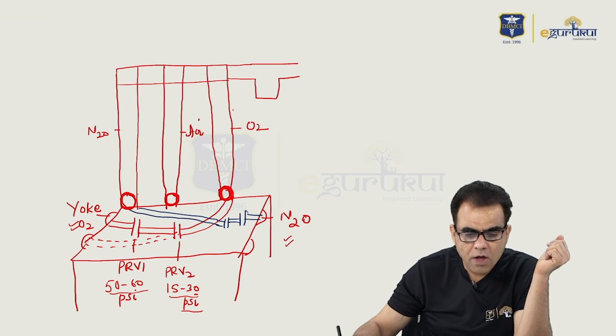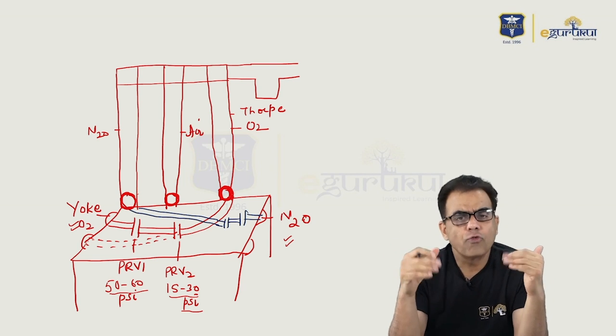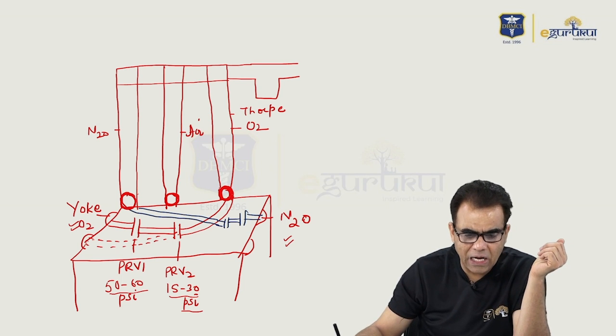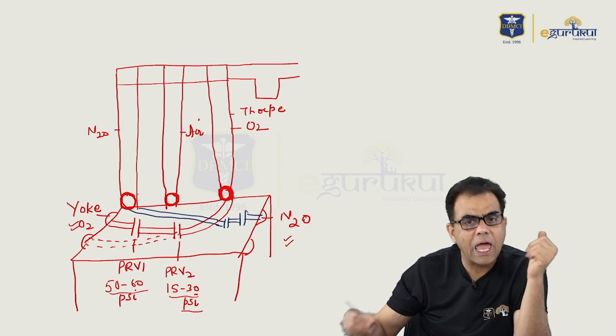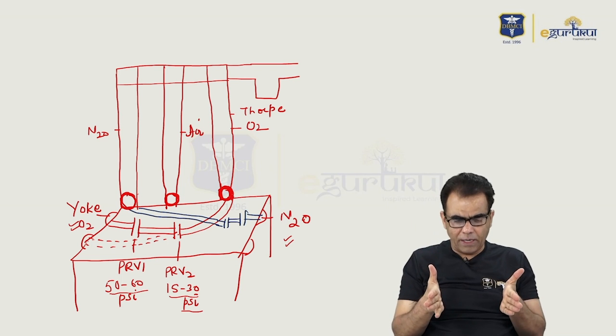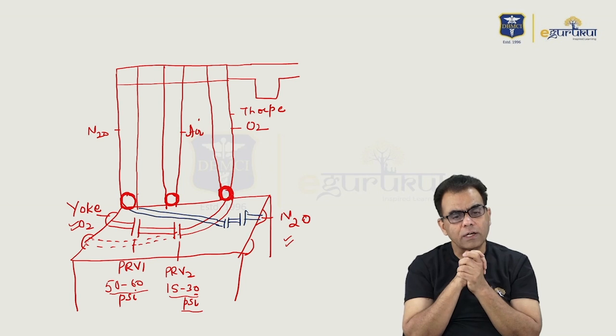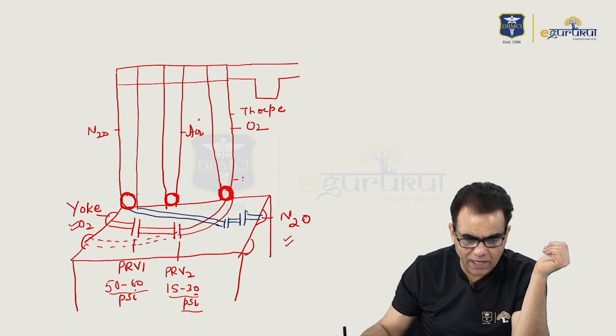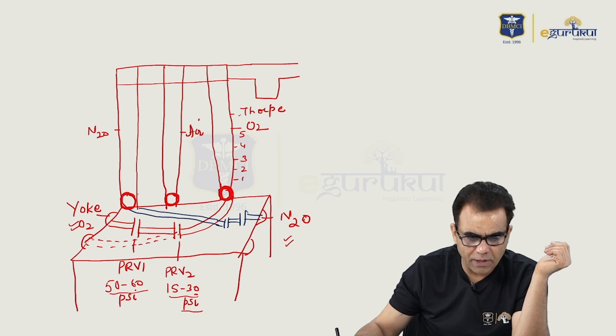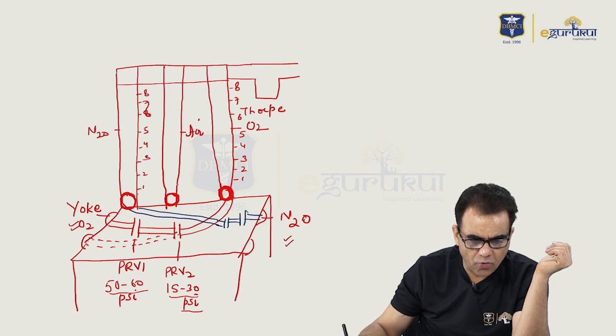These tubes were first described by the scientist Thorpe, so they used to be called Thorpe's tubes. However, nowadays they are just called flow meter tubes. These flow meter tubes are conical — narrow at the base and wider at the apex. Why are they not straight? So that they can accommodate more flows at the top. If the tube were straight, the height of the machine would significantly increase. These are glass tubes with markings indicating flow in liters per minute for oxygen, nitrous oxide, and air.